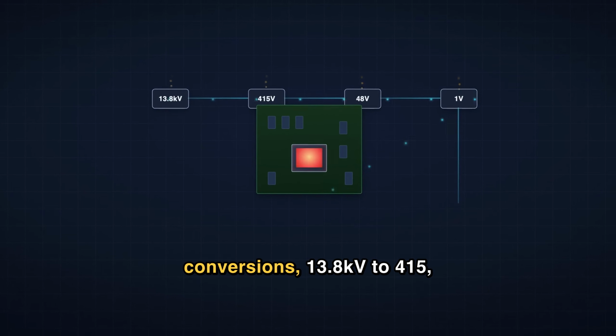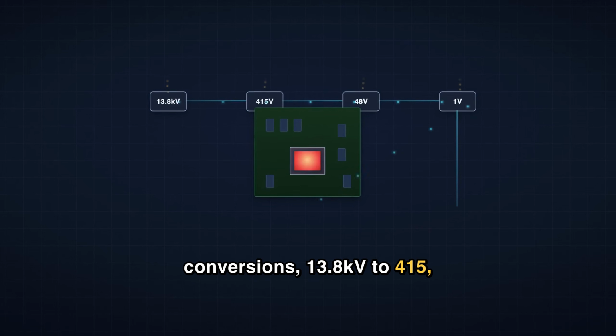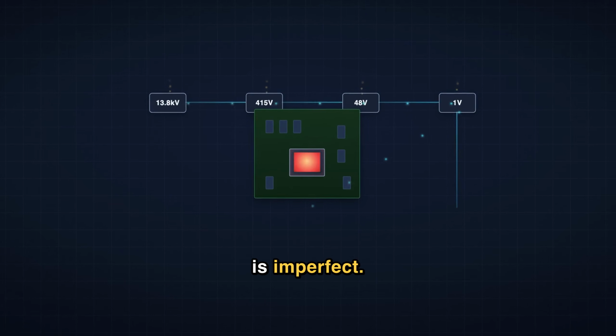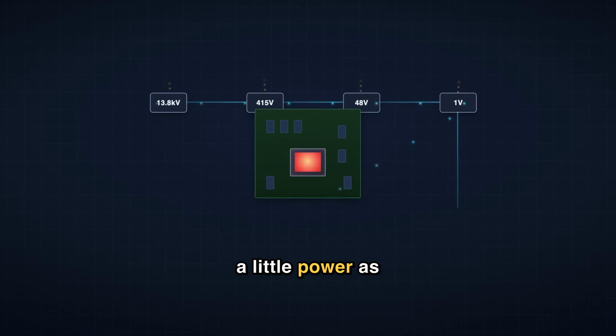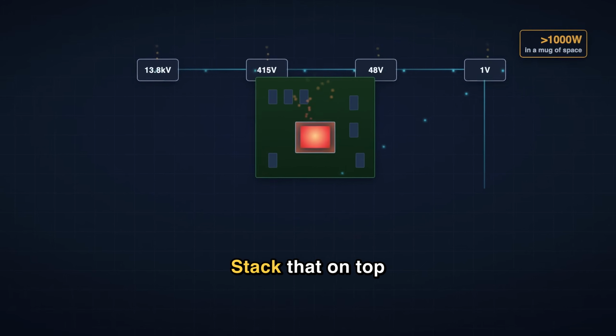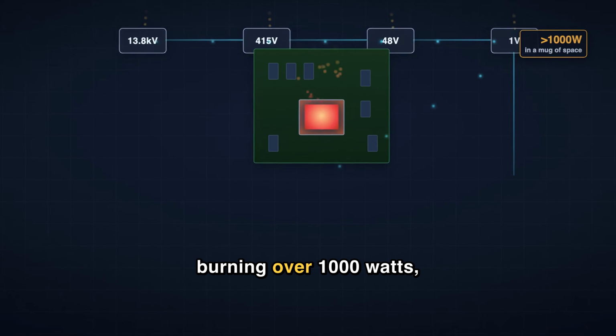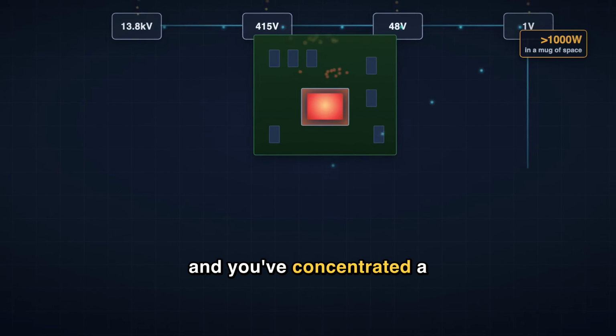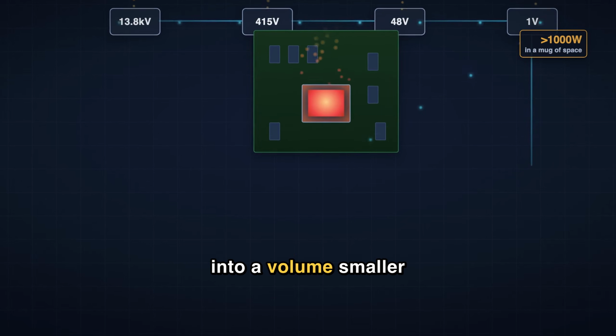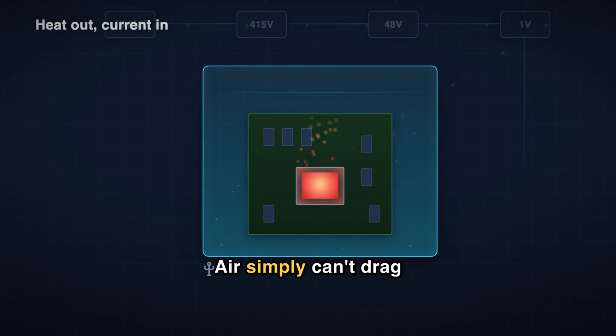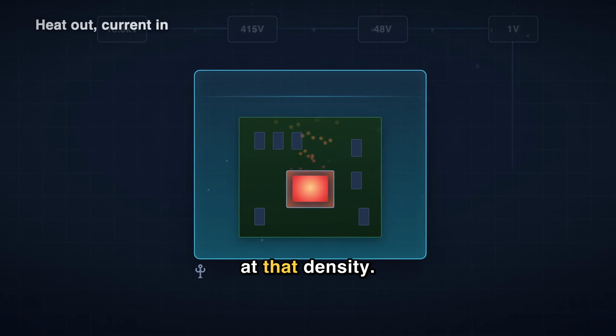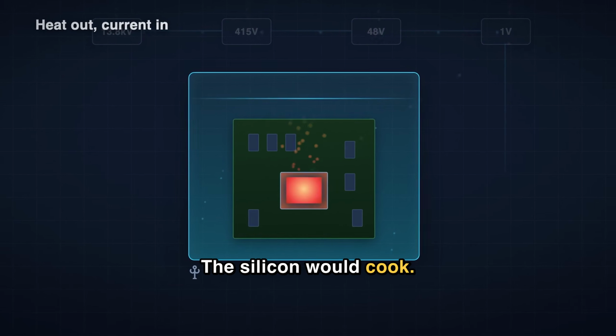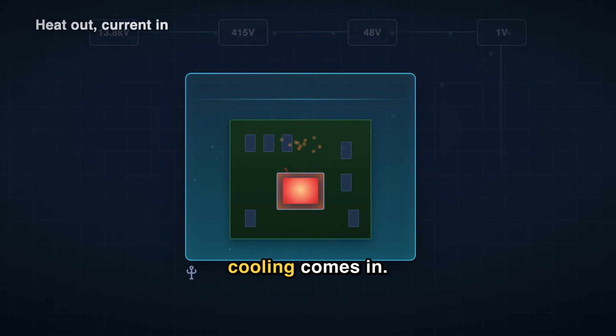Every one of those conversions, 13.8 kilovolts to 415 to 48 to 1, is imperfect. Each one skims off a little power as waste heat along the way. Stack that on top of a die already burning over 1,000 watts, and you've concentrated a staggering amount of heat into a volume smaller than a coffee mug. Air simply can't drag heat out fast enough at that density. The silicon would cook. This is where immersion cooling comes in.